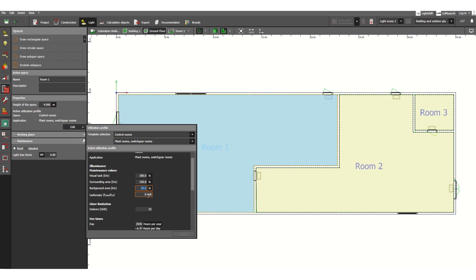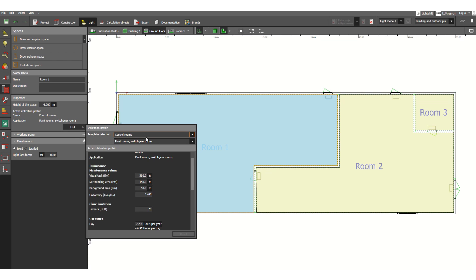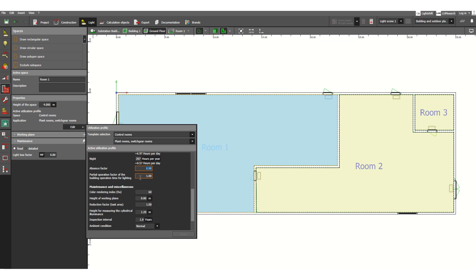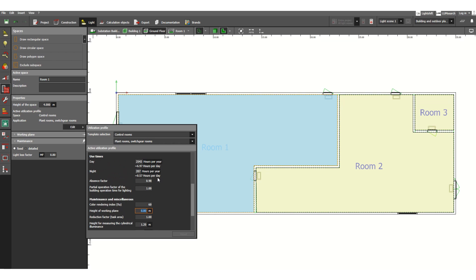The uniformity factor is E-min divided by E-m. This value is generally 0.4 to 0.6. The height of the working plane is 0.8 meters by default in DIALux Evo, meaning 800 millimeters from the floor level. You can change this height — if it is 1 meter, lux level will be calculated at 1 meter elevation.